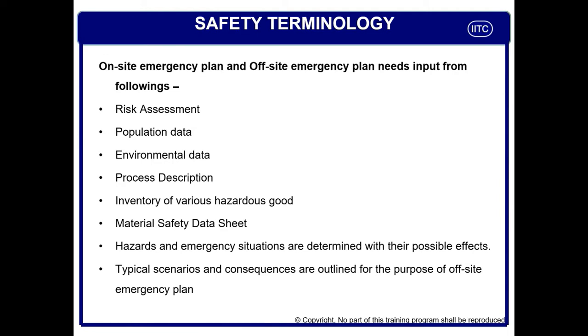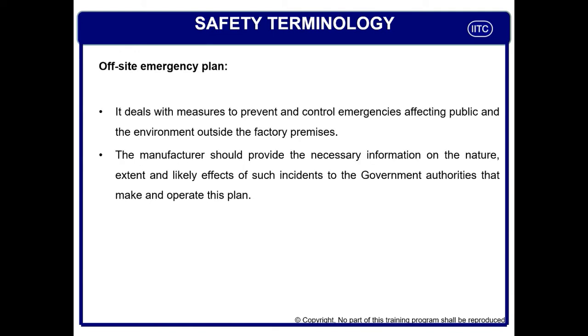Hazard and emergency situations are determined with the possible effect. Typical scenarios and consequences are defined and practiced in advance so that there is not much damage in case of any emergency. On-site emergency plan means those plans which define the methods to control damage if an emergency happens inside the plant and the emergency remains inside the boundary of your plant. Off-site means the moment any emergency which happens in your plant goes outside the boundary, then the off-site emergency plan comes into the picture.